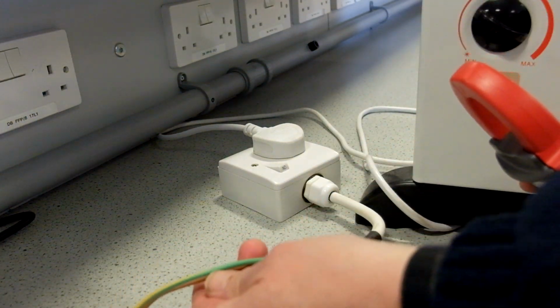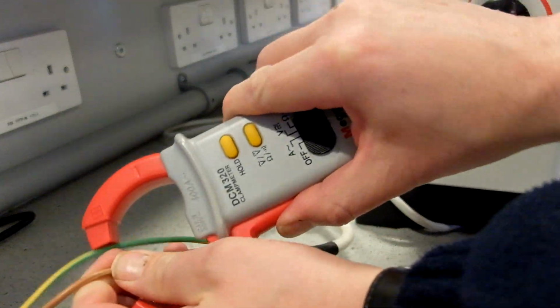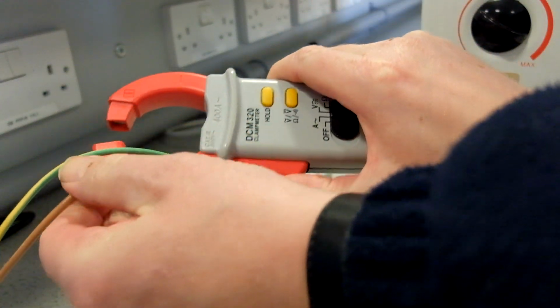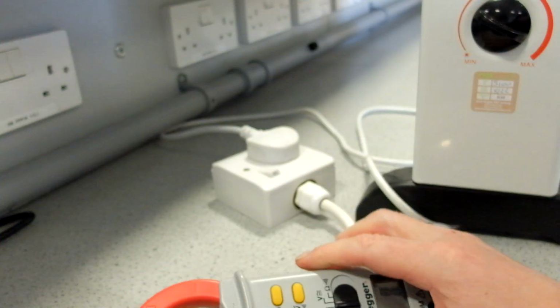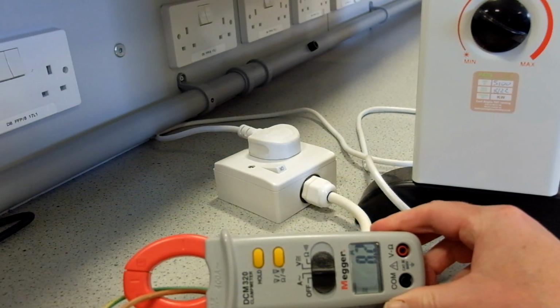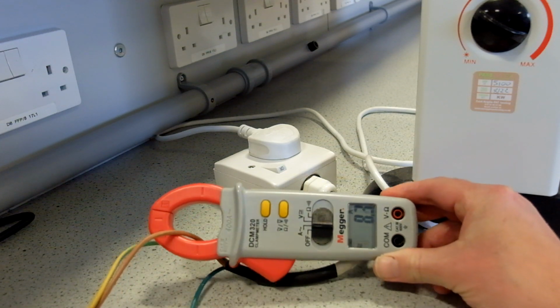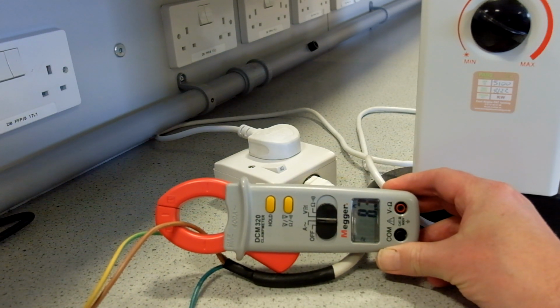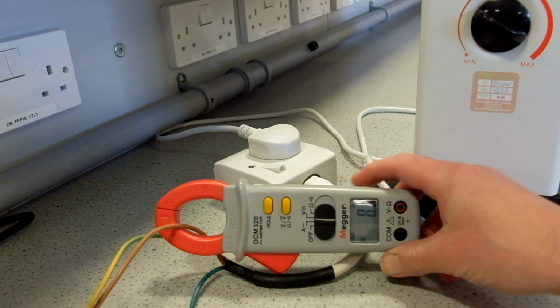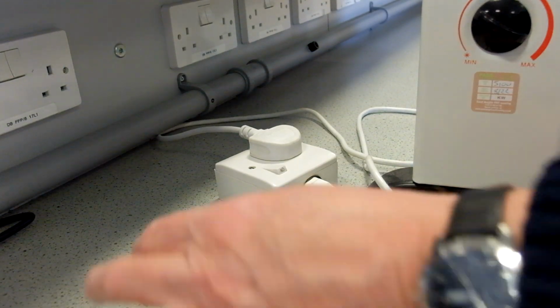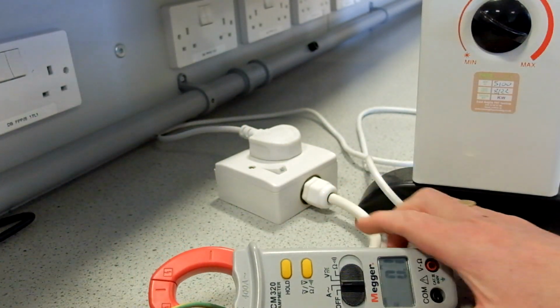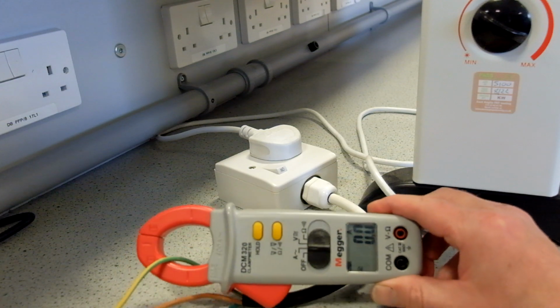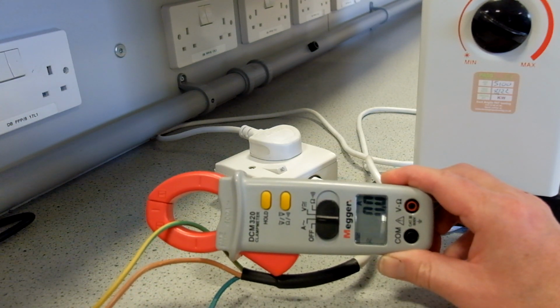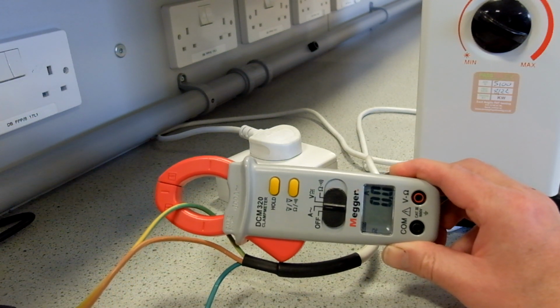If we go and measure clamp round the brown live wire, we should measure the same current. Current through the brown live should be exactly the same as it is through the neutral. We're measuring 8.2 there. If we measure current through the earth cable, what would we expect? We would expect 0 amps because the earth cable does not carry any functional current.